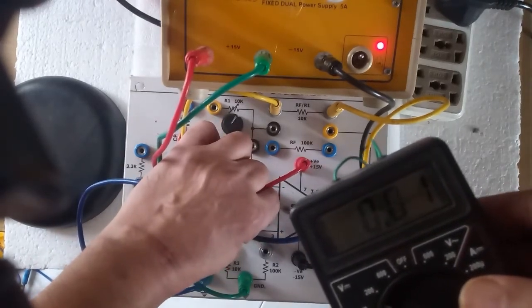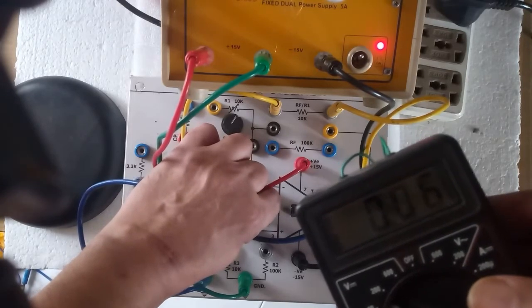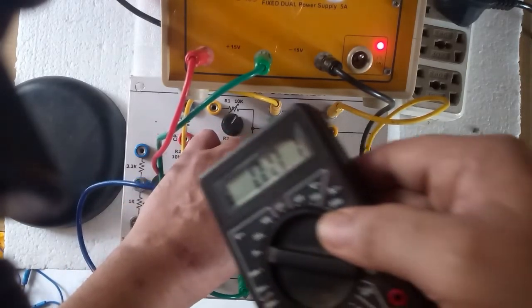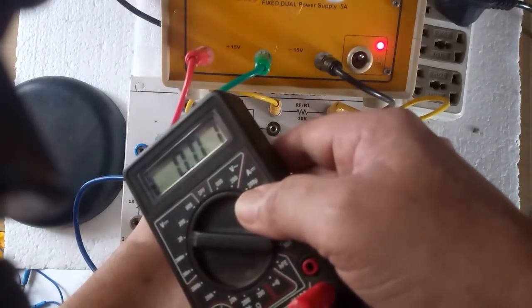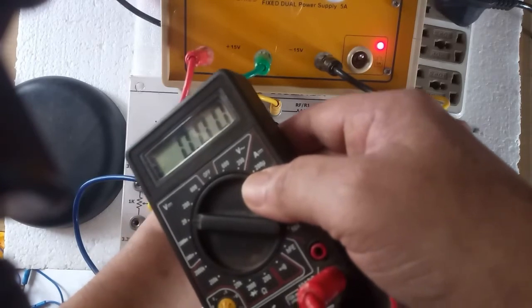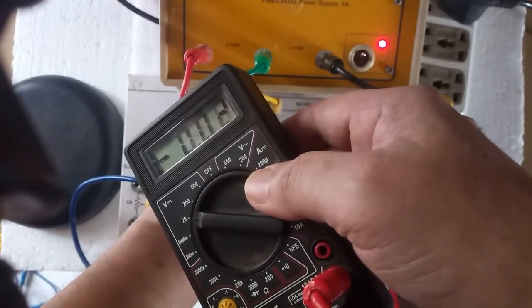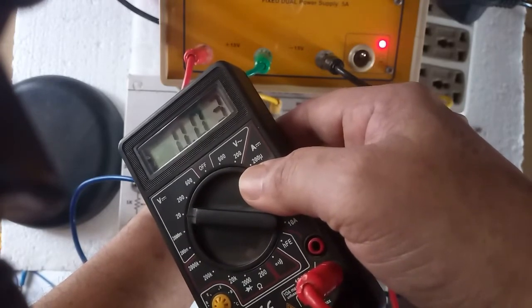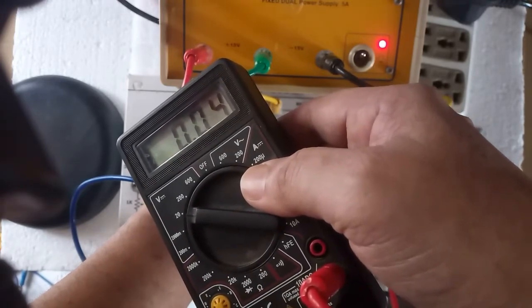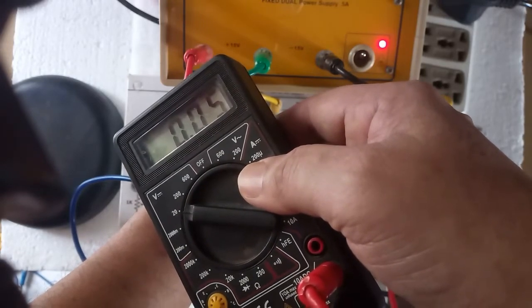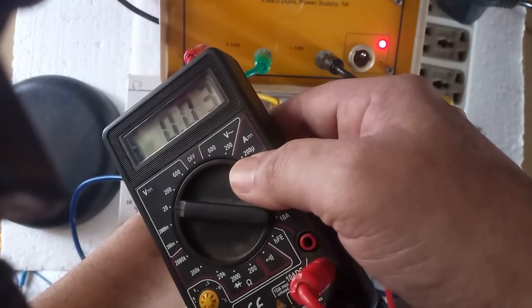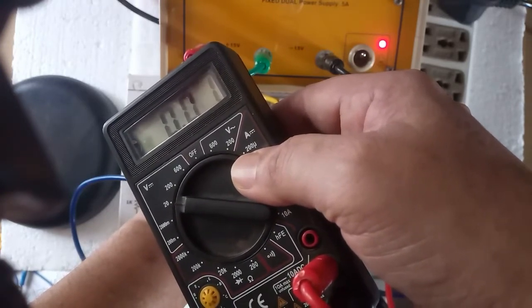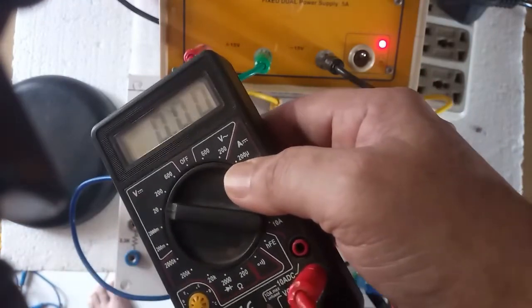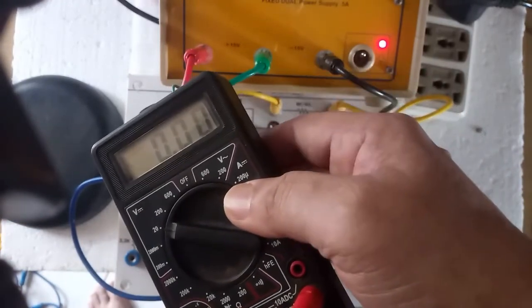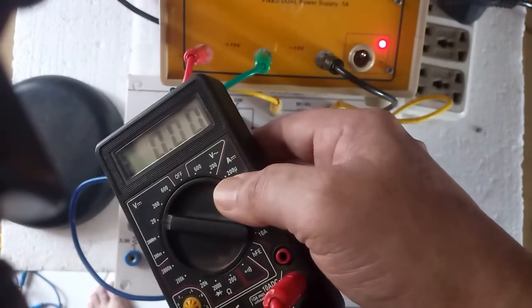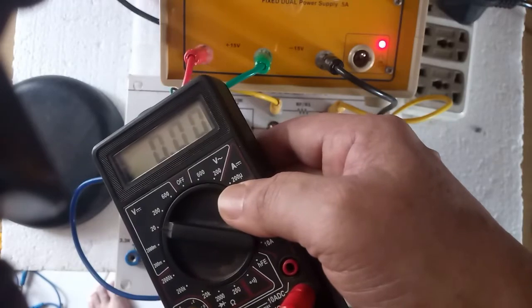So see, on the opposite side it is showing plus, this is plus, then minus, and in between somewhere you will find 0.00. So here you got 0.00. So this is the null offset adjustment.